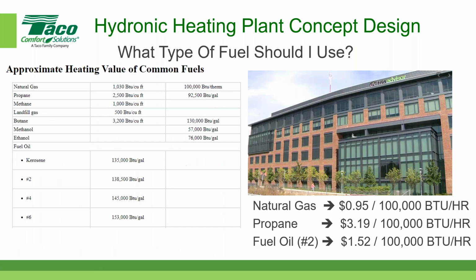Okay, so let's think a little bit about the heating value of fuels. I put this little chart together. I actually took a picture of this chart online. If you notice, natural gas is 100,000 BTUs per therm. That's the rule of thumb. And propane is about 92,500 BTUs per gallon. And if we go all the way down to fuel oil, the most popular fuel oil for heating a home is number 2. The number that I have here is 138,500 BTUs per gallon. Most people round that off and use 140,000 BTUs per gallon.